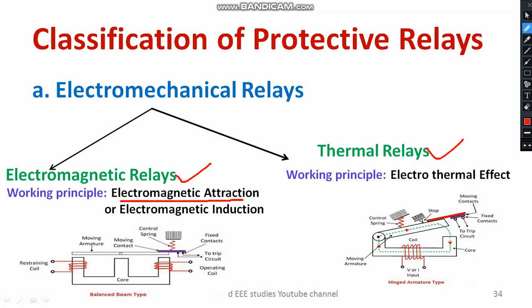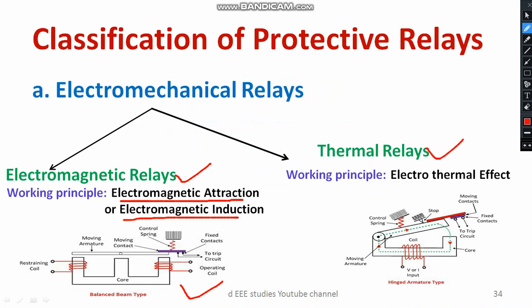You need to understand the difference between permanent magnet and temporary magnet. When a current is passed through a conductor, that conductor becomes a temporary magnet. Another principle is called electromagnetic induction. Looking at the electromagnetic attraction principle, we have a core material with an operating coil and restraining coil connected to the core, a moving armature, and a spring control mechanism. When current passes through the core, it becomes magnetic, attracting the moving armature towards the core. At that point the contact position changes, directly activating the trip circuit. If the magnitude of current is very high, the attraction rate will also be higher, activating the trip circuit.